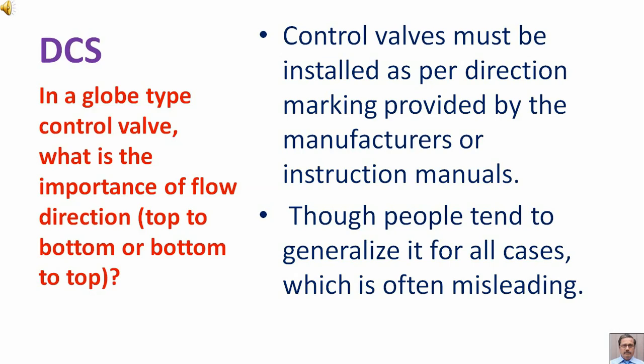In a globe type control valve, what is the importance of flow direction? Top to bottom or bottom to top? Control valves must be installed as per direction marking provided by the manufacturers or instruction manuals, though people tend to generalize it for all cases, which is often misleading.